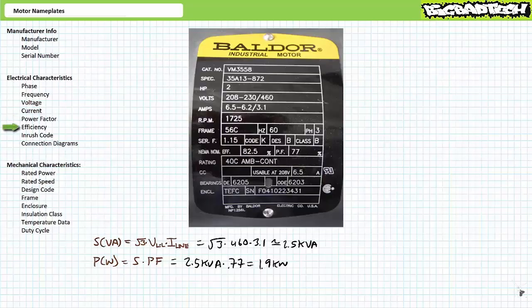While we've got this example in front of us, let's discuss efficiency. The efficiency entry on a motor nameplate specifies that portion of real electrical power input that is successfully converted into usable mechanical power output. Losses might include heat, friction, noise, among others. This motor nameplate indicates this 2 horsepower motor operates at 82.5% efficiency. 82.5% of roughly 1.9 kilowatts demonstrates the motor yields 1,569 watts, or roughly 1.5 kilowatts of usable mechanical power output.